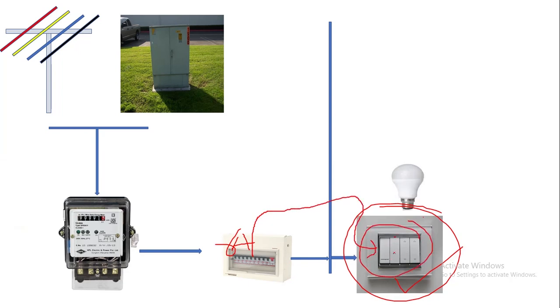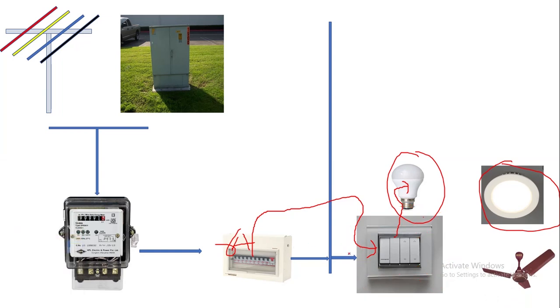From the 6 ampere MCB we feed the light circuit to the switchboard. From the switch we give power to our light loads — these are the light loads — and here we also have a fan. We can control the lights through individual switches. The neutral is provided directly and looped through to reach the light loads.